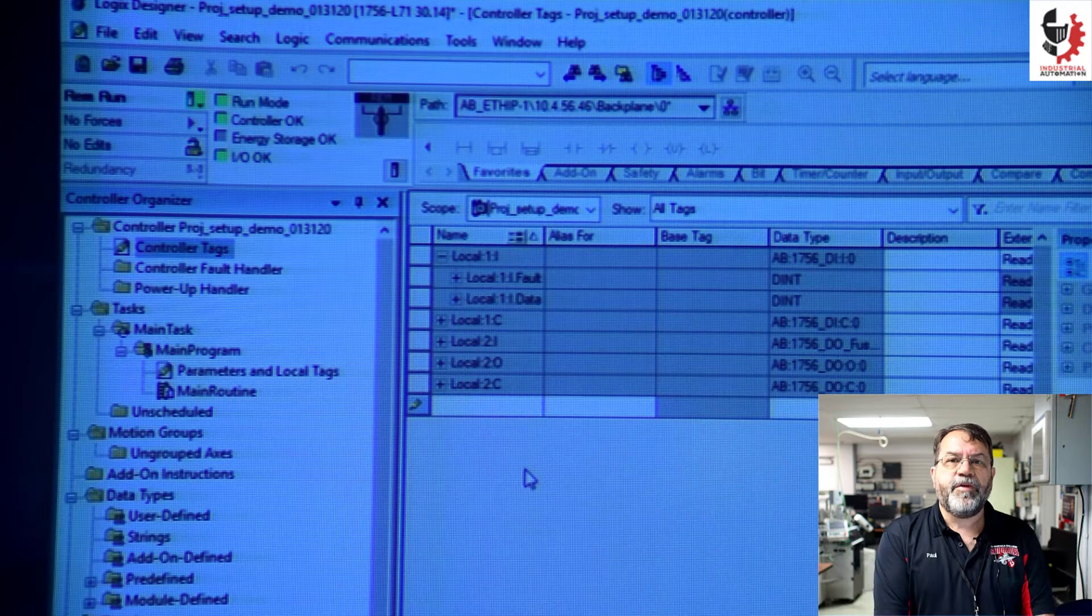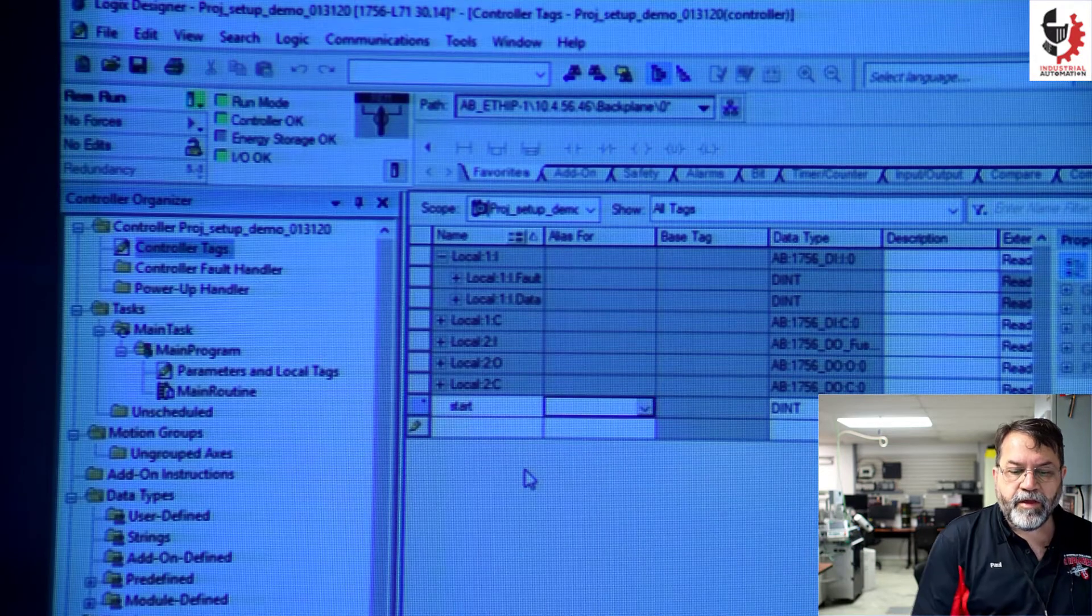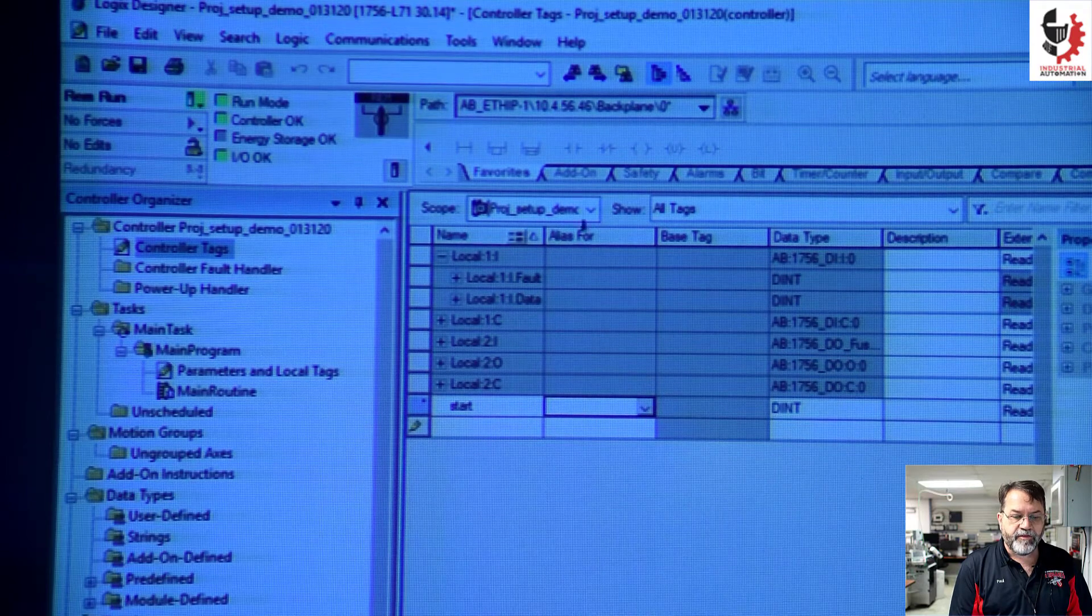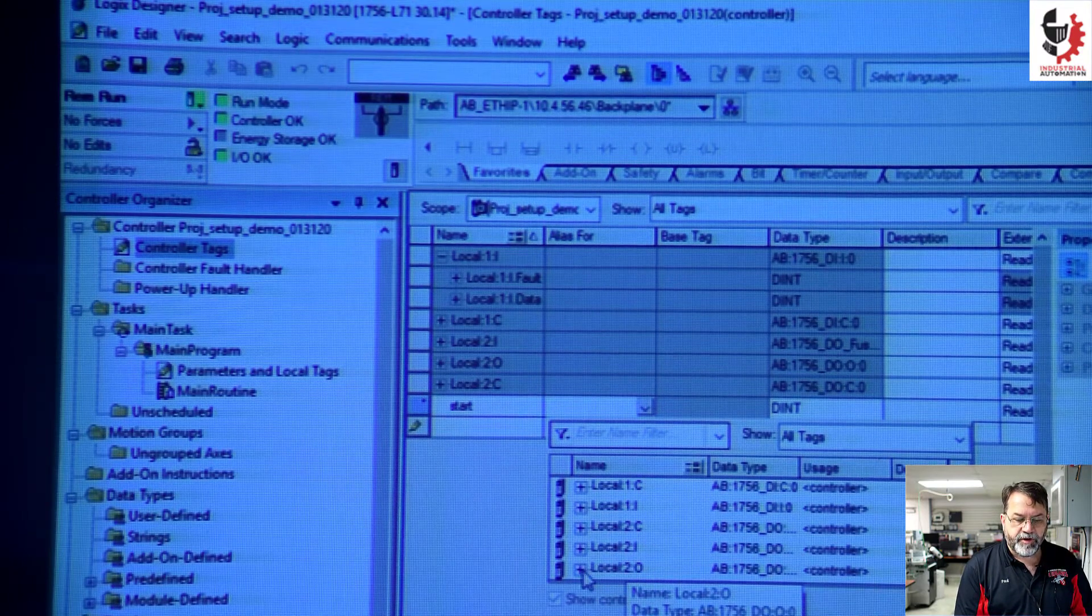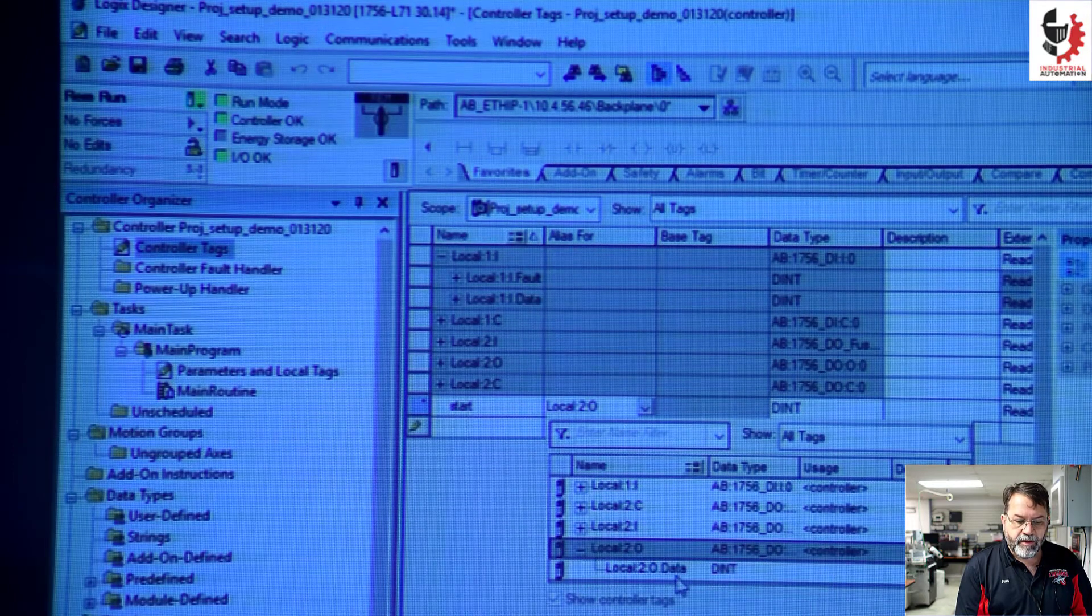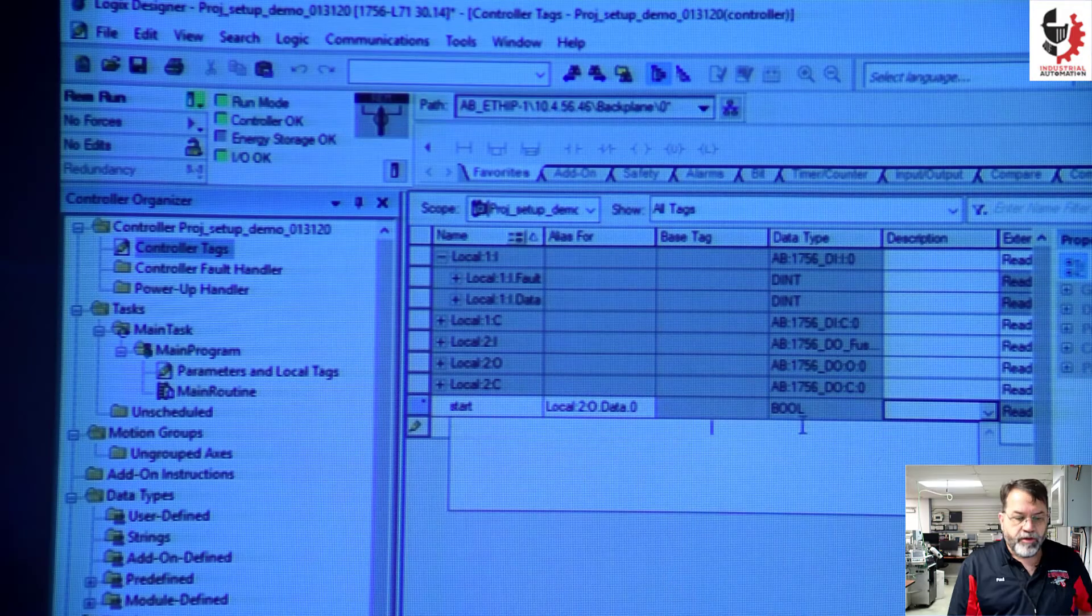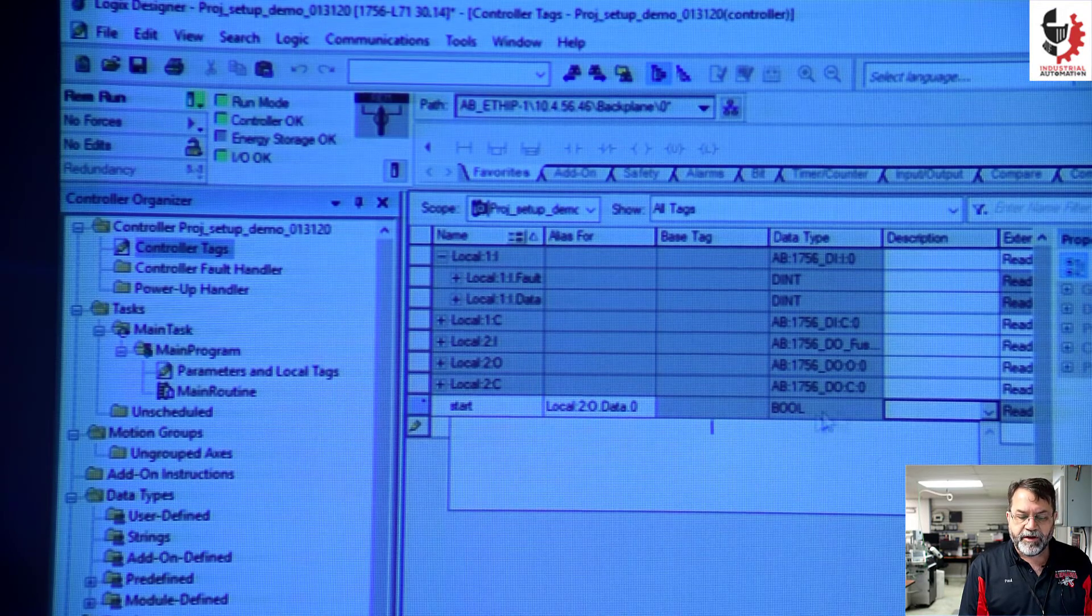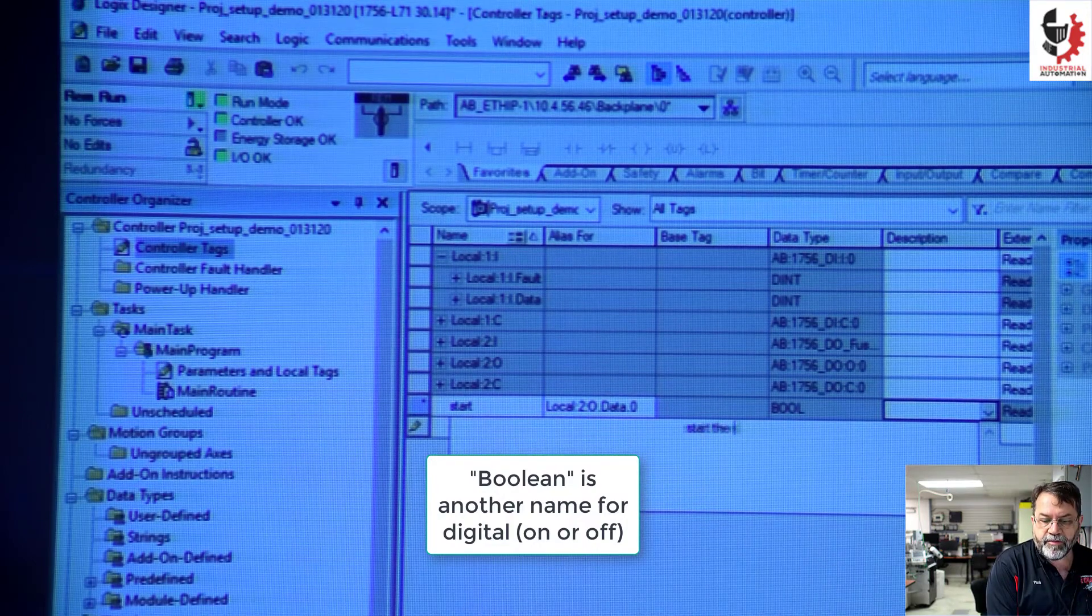Here I'm going to start making an alias tag. I'll call it start. And that's going to be an alias for one of my outputs. So here under alias, I'm going to click this dropdown. I'm going to find my output module, which is my second slot. So local two output. I'll expand that. And under data, I'm going to expand that and I'm going to use zero. Creating that alias tag and linking it to a physical output address automatically updated this to a boolean. Now I'm going to give it a description: start the machine.